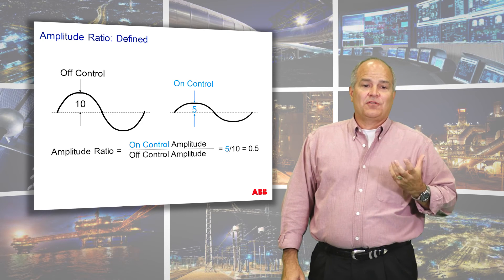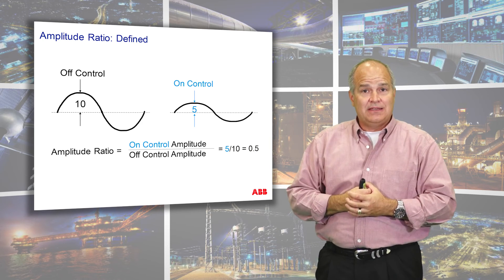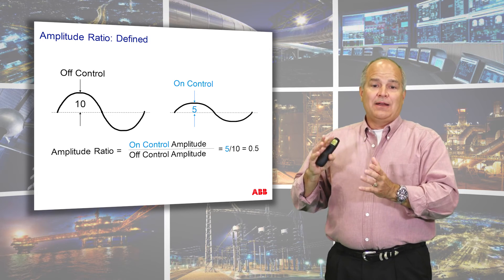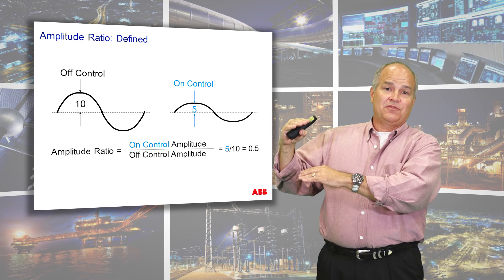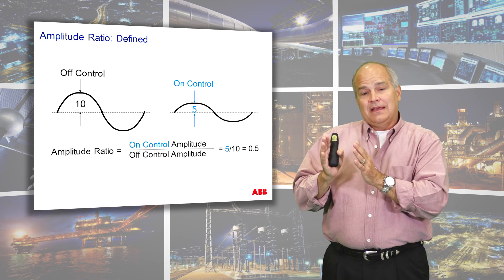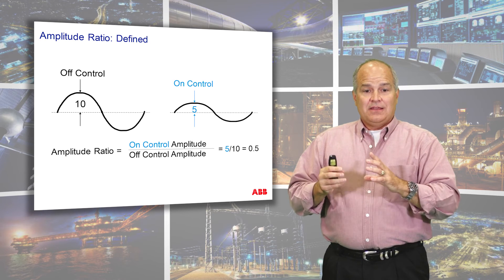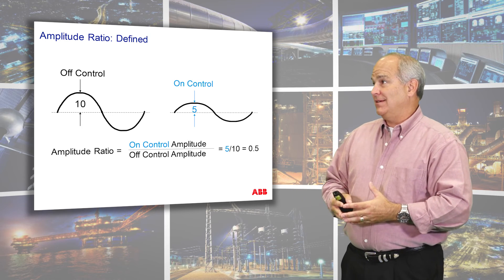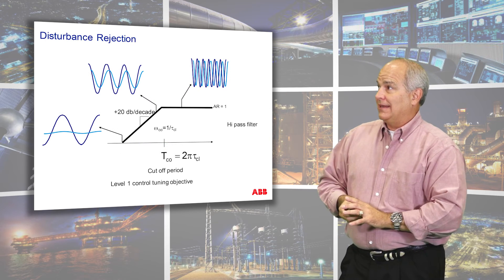For example, if my off-control process had an oscillation with an amplitude of 10 and then I turned the control on, I would expect — let's say — an amplitude ratio of 0.5 afterwards. And then depending upon the phase shift, you could actually calculate what the attenuation characteristics of that control loop actually are, which is an interesting theory.